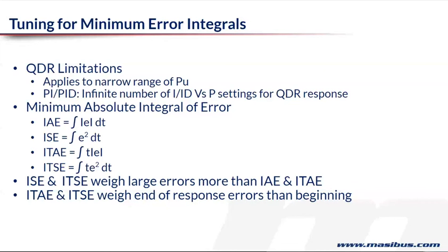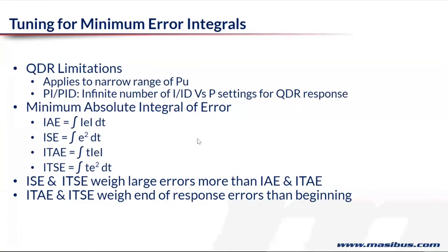Now, these different methods have different utility. I just explained, when it comes to a change of set point, you use the IAE method, because that method gives you minimum overshoot. Down here, the square of the error and the time weighted square of the error, you use when the impact will be more over large errors. So you are using the square of the error, because you quickly want to dampen the error.